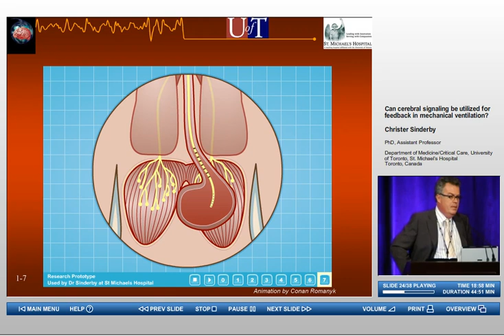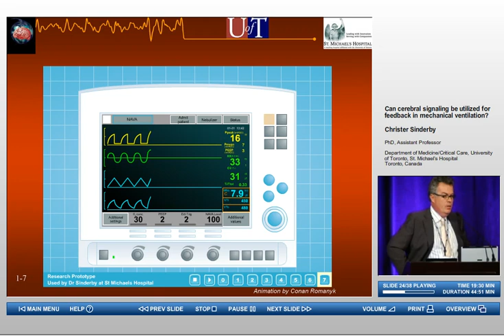And here you can see the mode as an animation. This is really what it does. At the bottom part you see the diaphragm activity. At the top part you see the airway pressure. And you can see that as the diaphragm activity goes up, the pressure goes up too. When we come to the end of inspiration, we go back to PEEP. We have no assist during exhalation. There is only PEEP. And you can see here was a bigger breath. So you got a bigger effort and you got more assist, which helped you to increase your volume and flow. So this mode is interacting with you within every breath and between breaths.